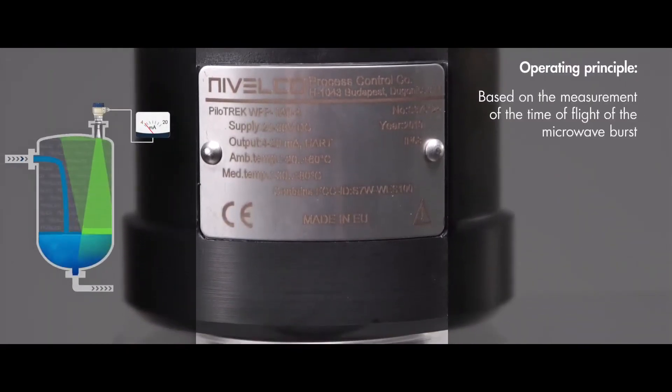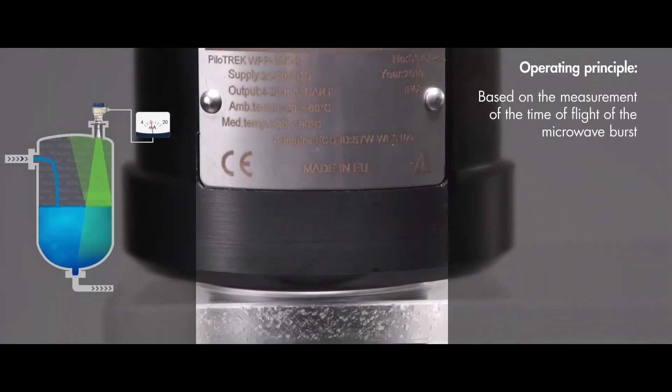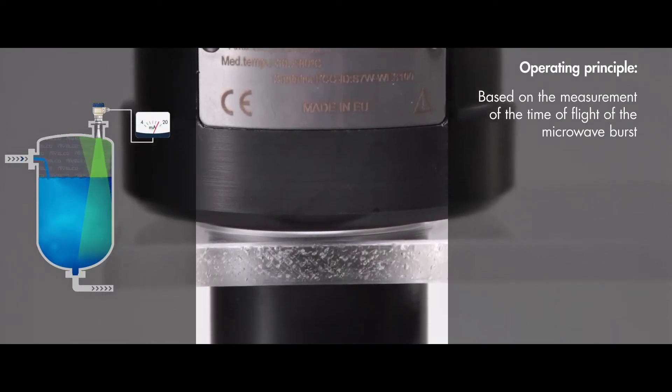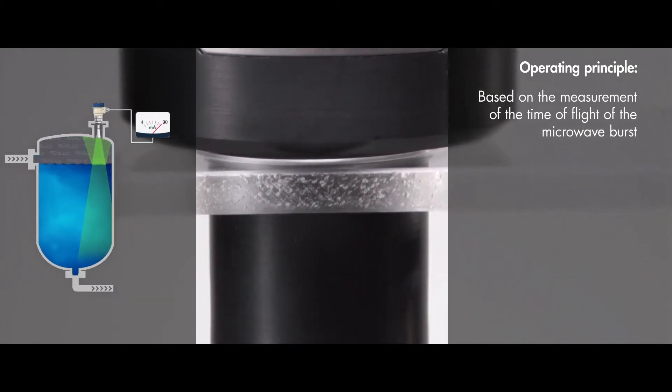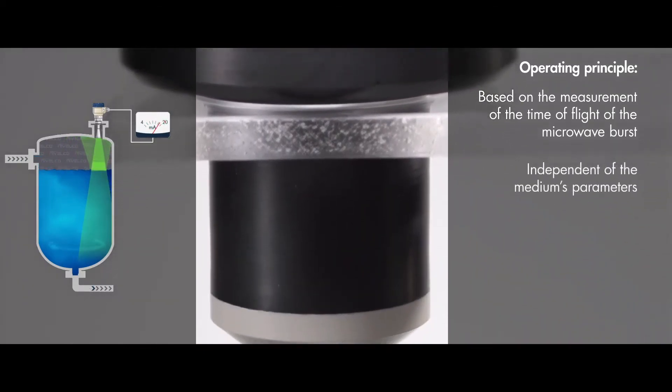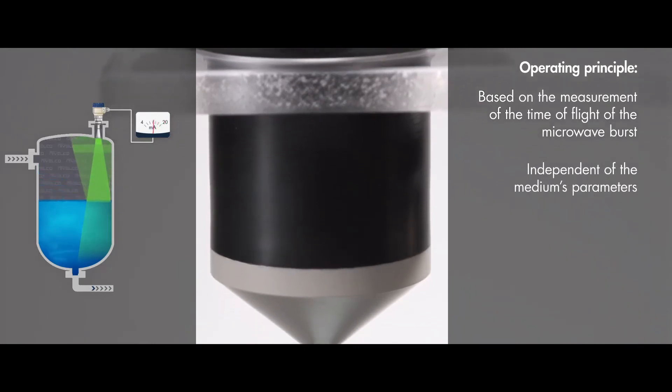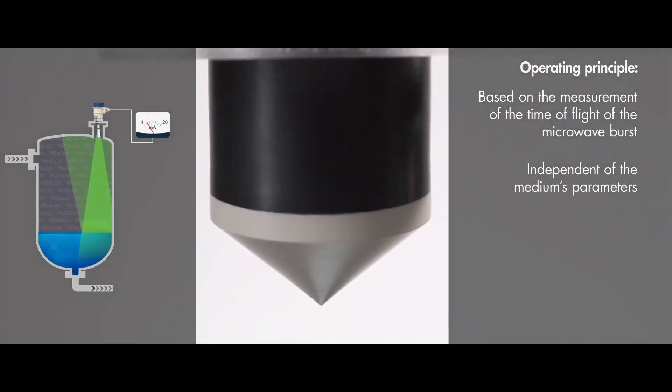Operating principle. Same as other PiloTREK model's operation, which is based on the measurement of the time of flight of the microwave burst reflected back from the surface of the medium. The measured value is not affected by the physical parameters of the medium.